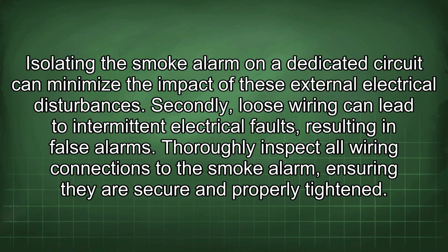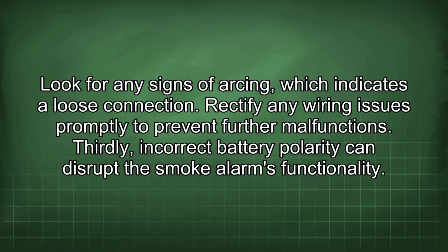Secondly, loose wiring can lead to intermittent electrical faults, resulting in false alarms. Thoroughly inspect all wiring connections to the smoke alarm, ensuring they are secure and properly tightened. Look for any signs of arcing, which indicates a loose connection. Rectify any wiring issues promptly to prevent further malfunctions.